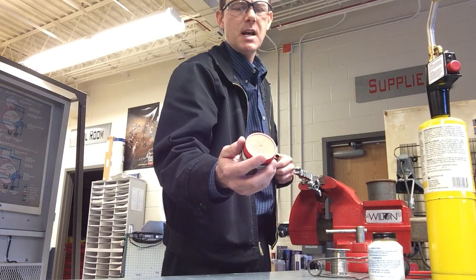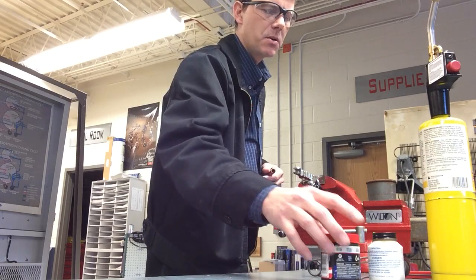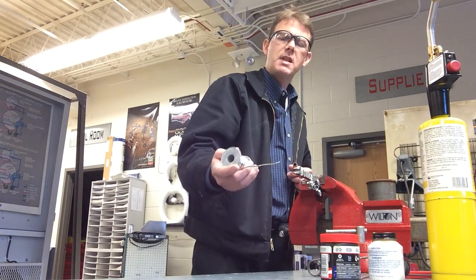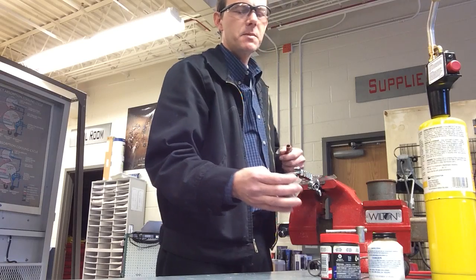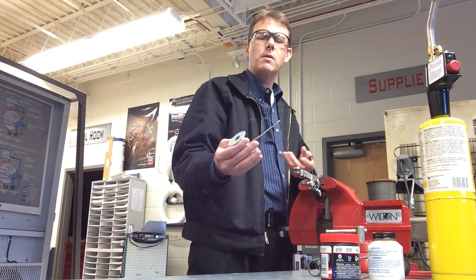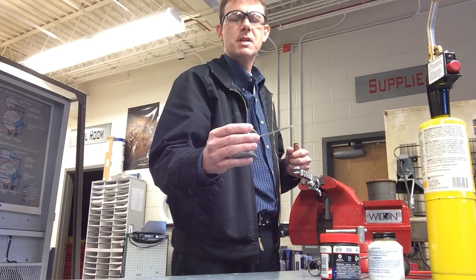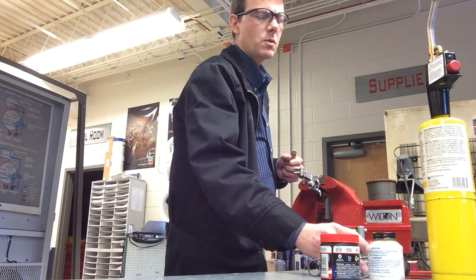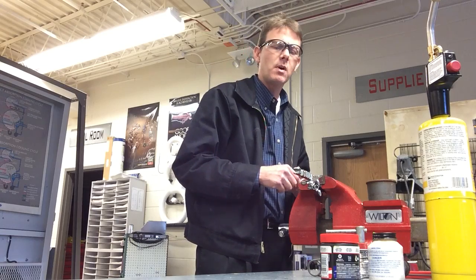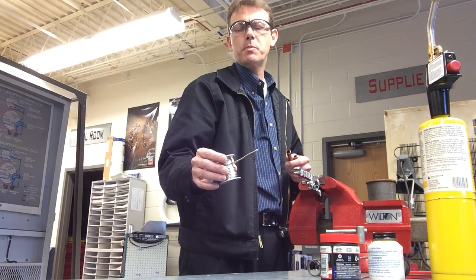The flux prevents oxidation, though it does do some cleaning as well. We'll be soldering with 95.5 solder — 95% tin, 5% antimony. If you're using a stationary water line for an ice machine or something that's not going to be moving around, you can probably get away with 95.5 solder. If you're using something connected to a pump or something that's going to vibrate, you might want to use Stay Brite solder, which has four percent silver in it — a silver-bearing solder.